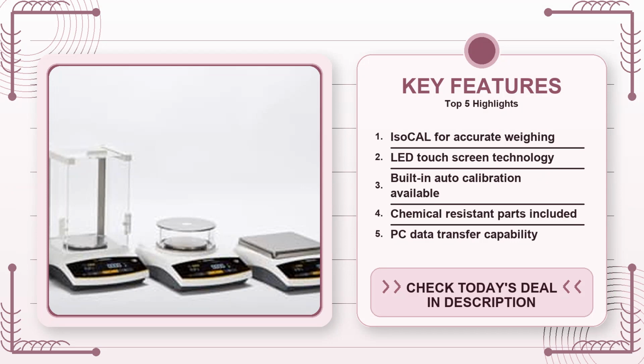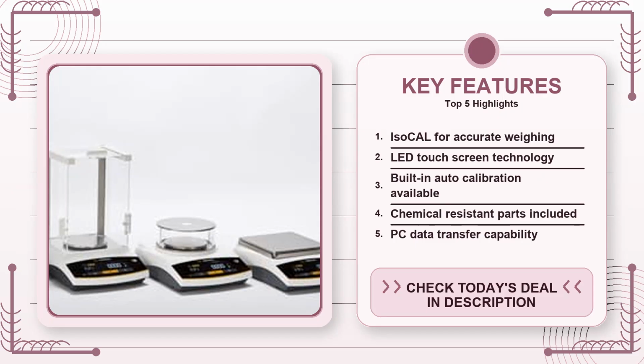For these users, the IsoCAL feature can be a real time saver. Because the balance can self-calibrate internally, you don't have to pull out a set of external weights each morning. In practice, that means you can start a series of weigh-ins within minutes of powering the unit on, and you'll have confidence that the numbers are drifting less than a fraction of a milligram over the day.